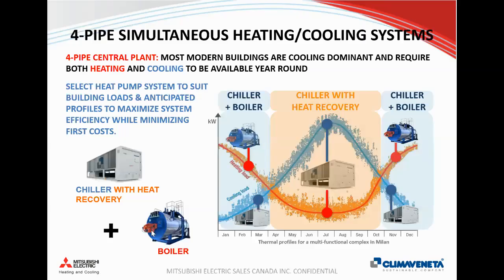The only other thing I wanted to cover is that 4-pipe systems are most common. There is a class of heat pumps called 4-pipe simultaneous heating and cooling heat pumps that can provide both hot water and chilled water, performing heat recovery at the same time. Those are typically more expensive. You may not necessarily need that in your building. You might want to look at a chiller with heat recovery. But again, the main point here is to look closely and understand how the building's going to operate and work.